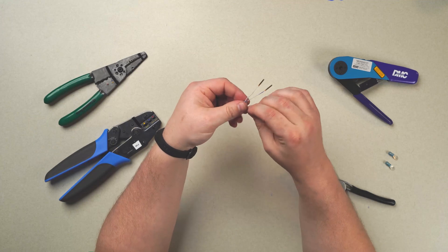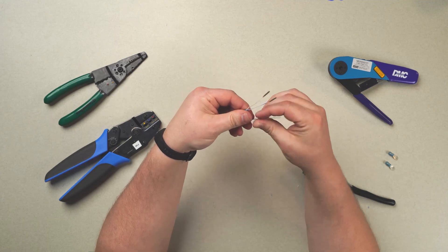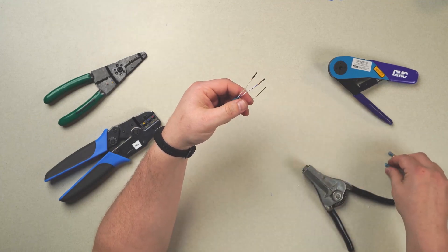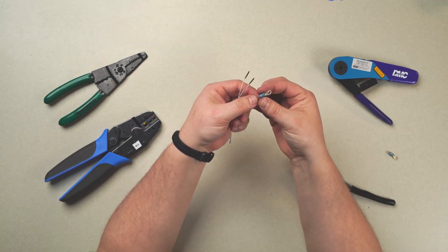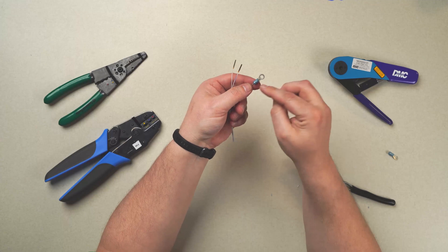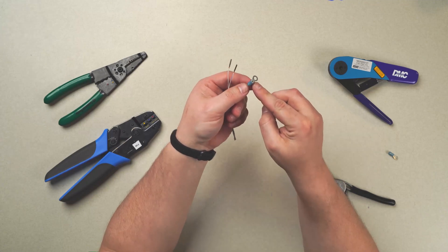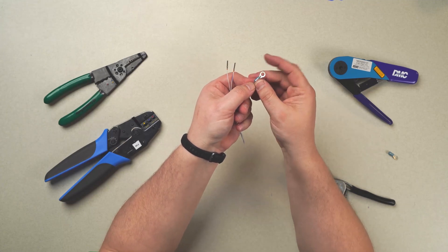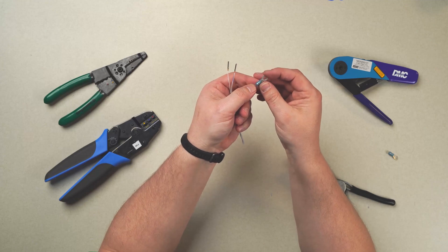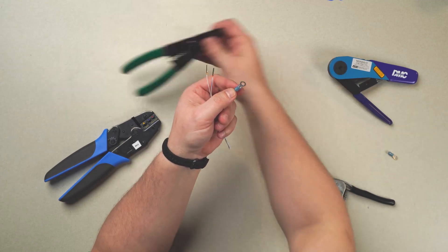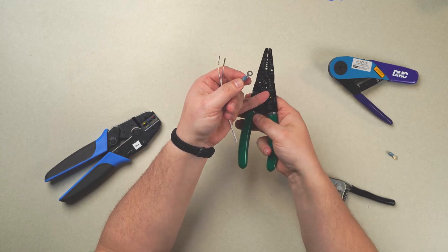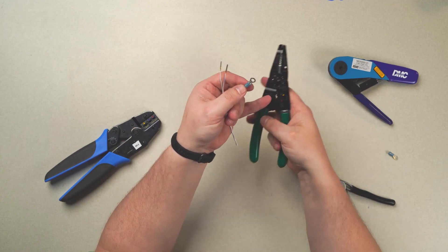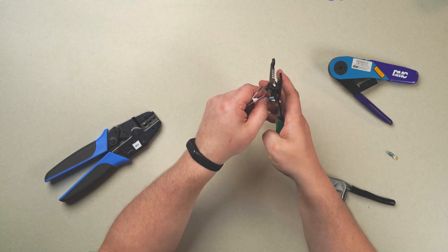Next, let's go ahead and crimp on our shield termination. First off, we're using the appropriate size. We want to make sure that we see exposed shield through the actual ring terminal itself. You see it goes all the way through. And we essentially have two options available. We have the hardware store option, which we'll utilize. This is a blue sleeve. We'll utilize the blue crimping position.